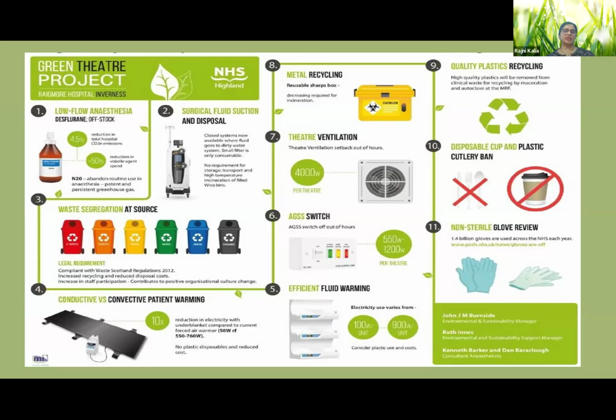The anesthetic gas scavenging system switch was turned off at some hours of the day so that it saves the energy being used. The theater ventilation was also set back for some hours of the day so that it saved 4000 watts per theater of energy. Metal recycling, reusable sharps boxes were reused again. Quality plastic recycling, if plastic can be reused, a ban on disposable cups and plastic, and limiting the use of non-sterile gloves so that it can reduce the plastic generation.